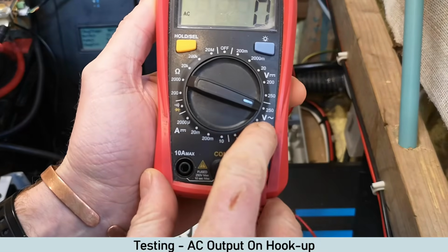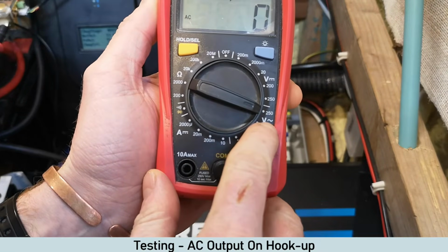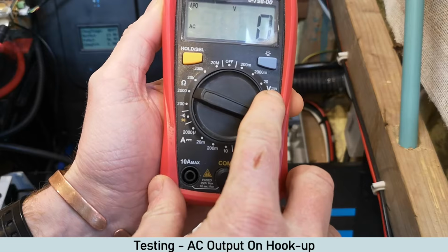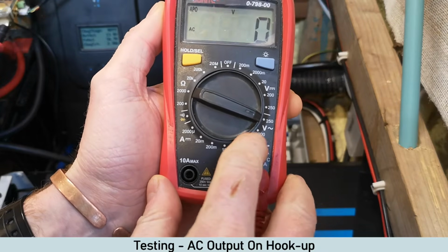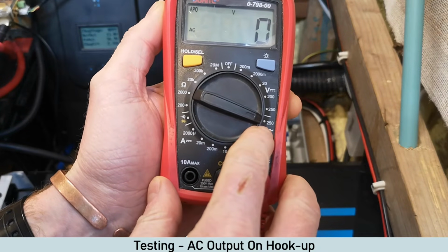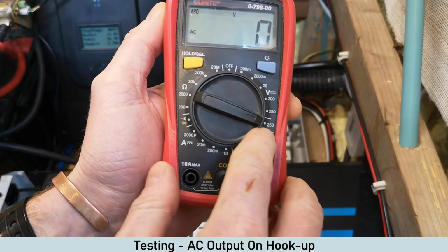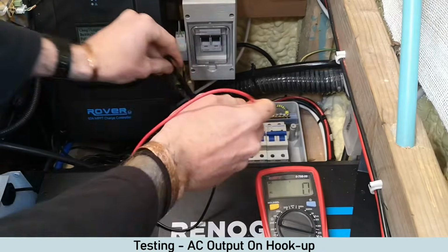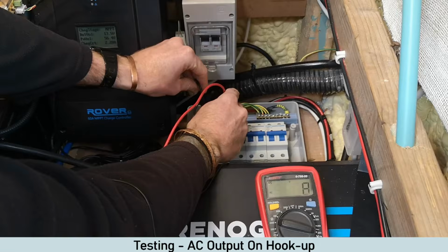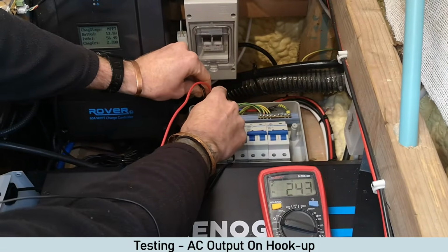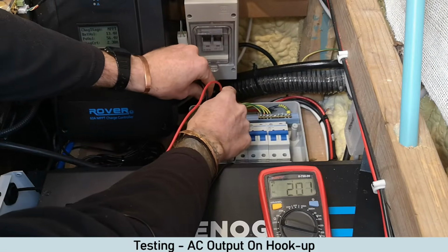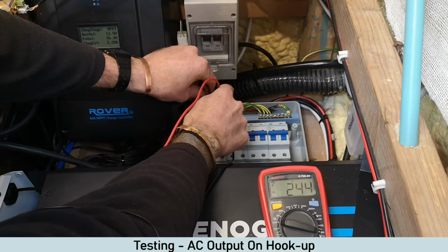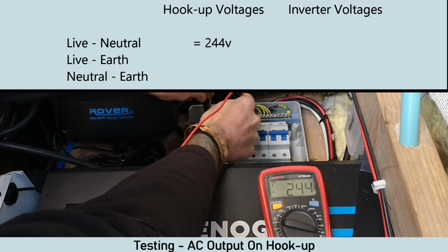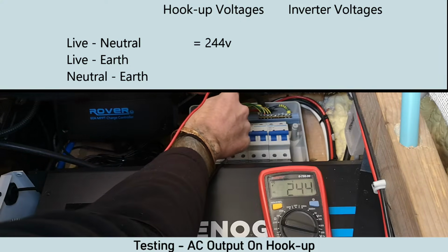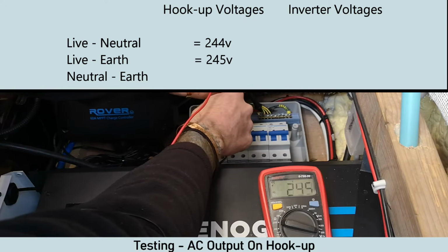You want to set it to AC volts. AC is the squiggle, DC is the flat line there, and 250. So we're going to be reading 230 volts, and that's a rough maximum of 250. What I'll do is go from live to neutral, which is quite high actually, which gives us 244. And then if I go from live to earth, that should give us roughly the same, 245.